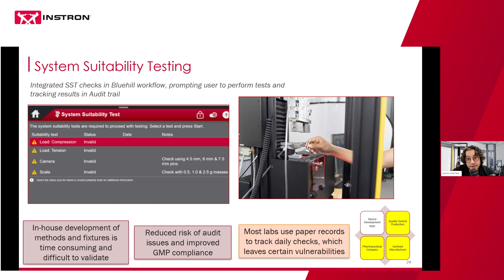Since you're already going to be in Bluehill, it makes sense to have this process embedded into the software anyway. And the nice thing is it doesn't prevent you from using your existing process. You can build your process into a method in Bluehill, and then prompt that method to be run for system suitability. So it's just automating that requirement to do these tests and preventing running the system for the day until these tests have been performed.